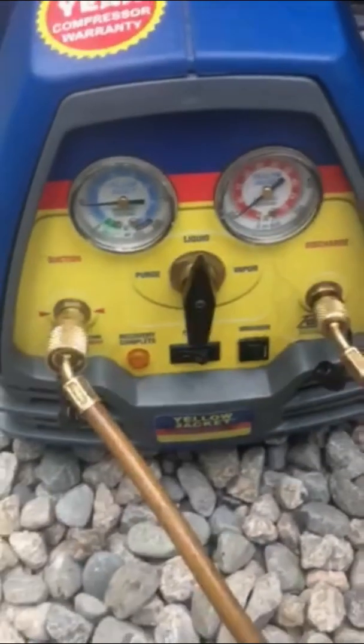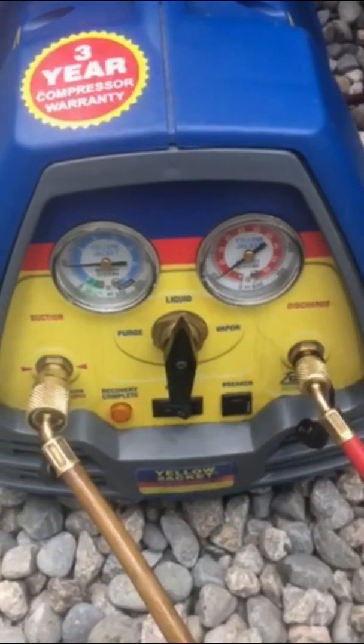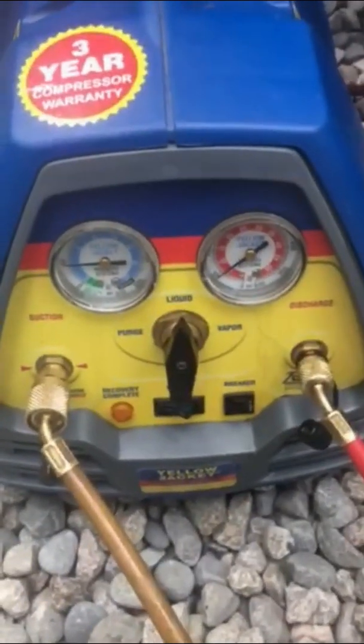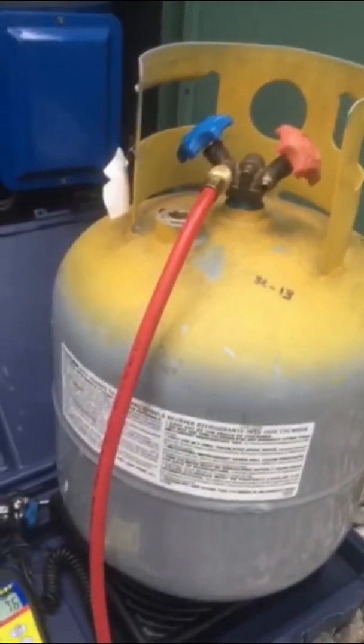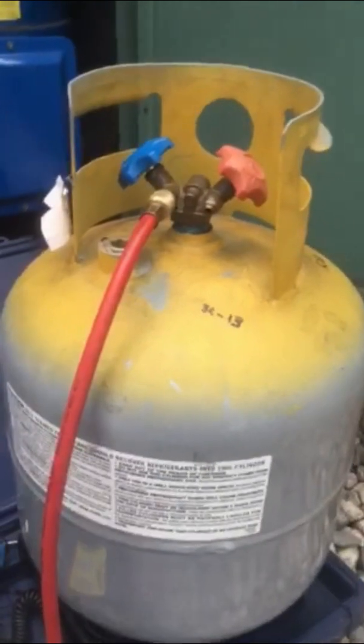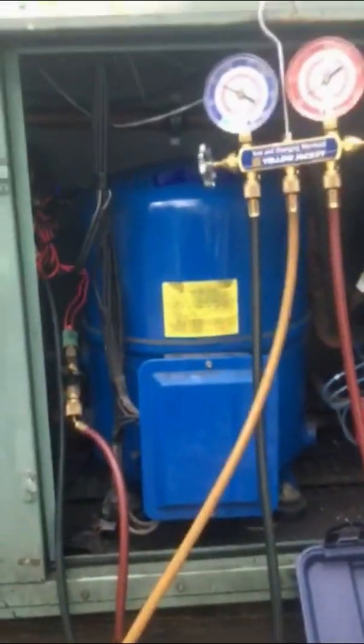This is a Yellow Jacket recovery machine — it's pretty great, we've had it for about five years with no issues. Most important thing: make sure you purge those lines so you don't get any air in your bottle and contaminate your refrigerant. Sometimes we put a filter drier on here to clean out contaminants, but the system's pretty tight so we're not worrying about that today.